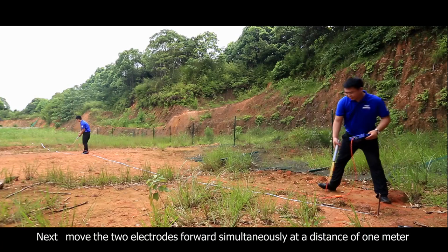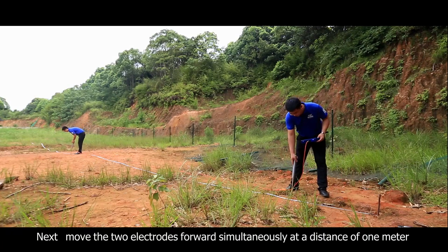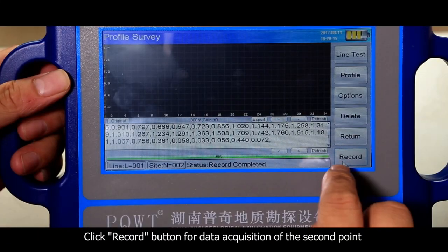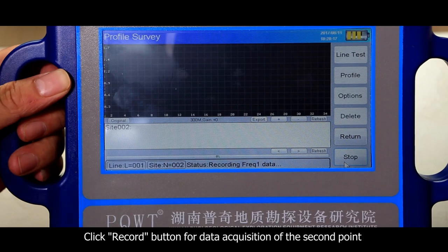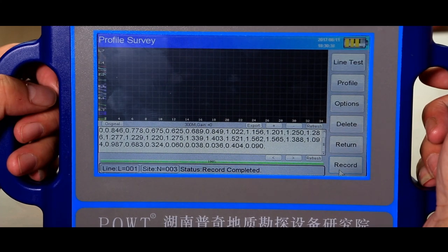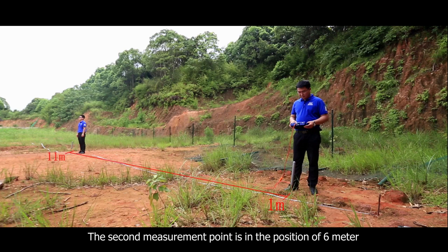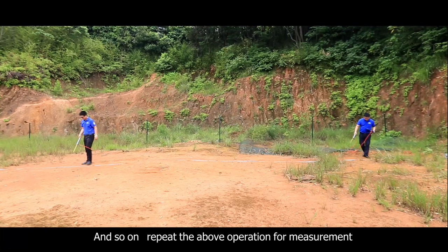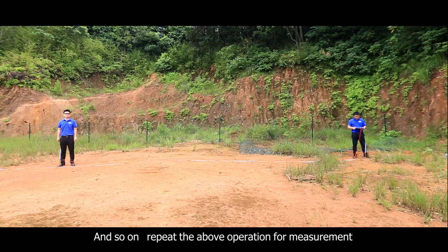Next, move the two electrodes forward simultaneously at a distance of 1 meter. Click Record button for data acquisition of the second point. When the acquisition is completed, the instrument display will notify record completed. The second measurement point is in the position of 6 meter. And so on. Repeat the above operation for measurement.